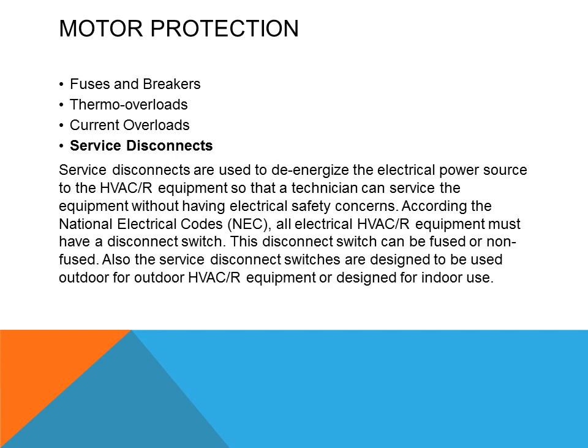Service disconnects are designed to allow a technician to turn off power to equipment for servicing. They de-energize the electrical power source to HVAC equipment so the technician can work safely. According to the National Electrical Code, all electrical HVAC and refrigeration equipment must have a disconnect switch. This switch can be fused or non-fused, and can be designed for outdoor or indoor use, each handling different types of current flow.